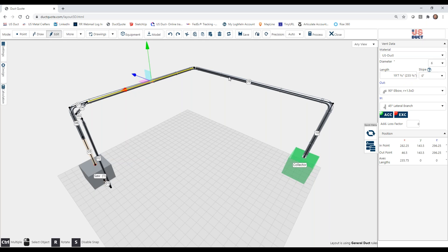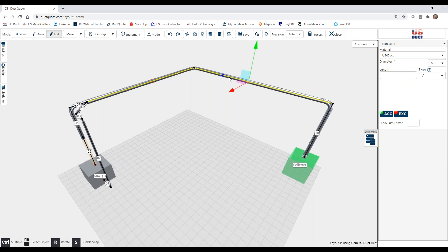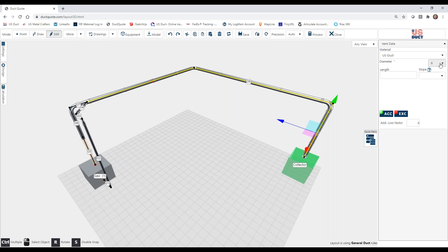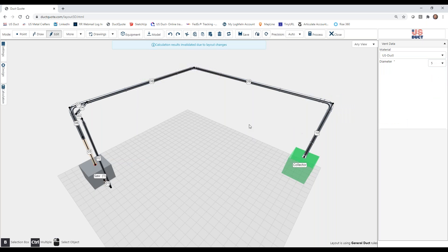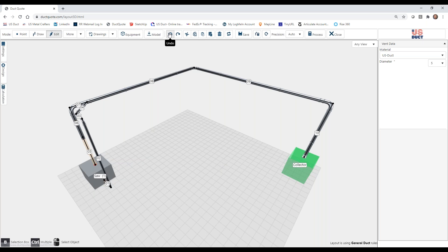Let's pretend that we wanted, in fact, to have a higher velocity within that. We can actually force a higher velocity by selecting the sections and then changing the diameter. As you can see, we do have control over the diameter. We are simply being told that the calculation results are no longer valid, and we would have to recalculate.